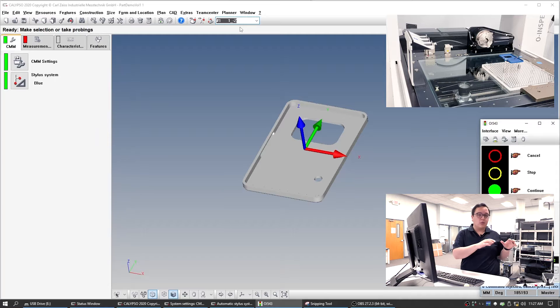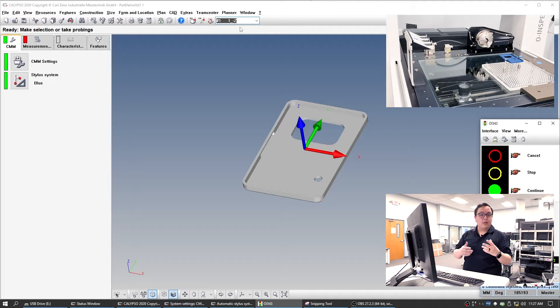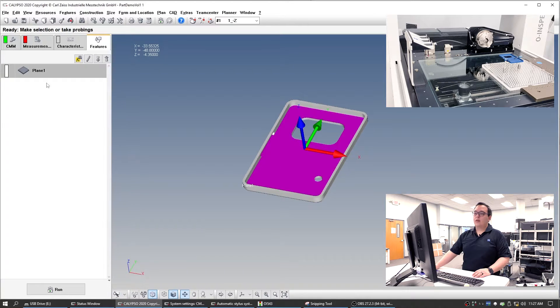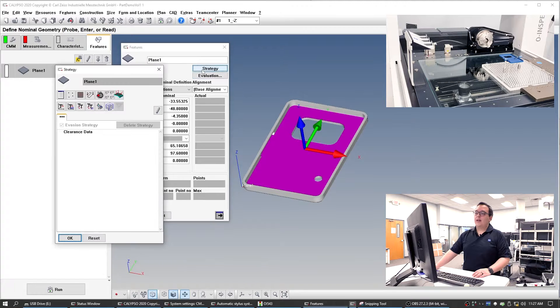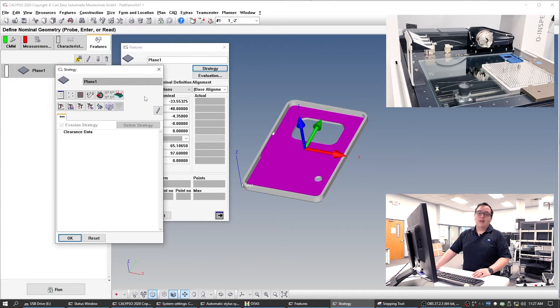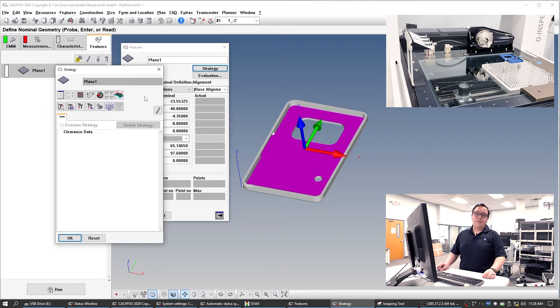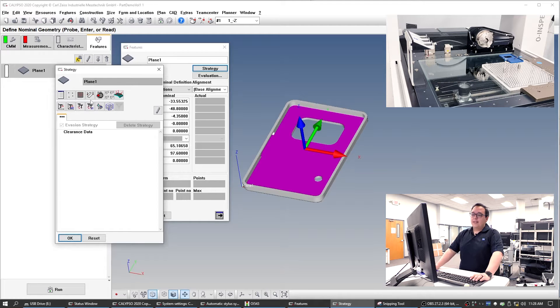I'm going to switch to using the correct stylus direction. We're going to start with Z — the one pointing down — because we want the biggest feature to be the one that we start probing from. So let's go ahead and define that geometry. We have to create a strategy for it. Something we have to keep in mind is the fixturing that we're using — we want to make sure that we jump over these little holders here, but capture as much of this as possible. One of the goals here is to make sure that it's as flat. Let's collect a couple points and then make a polyline from this.